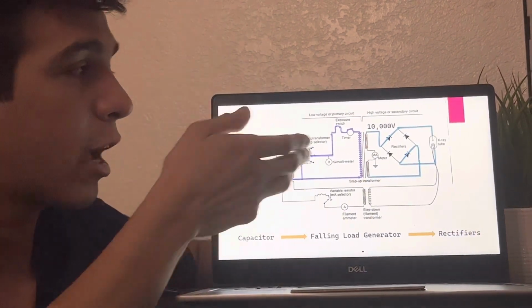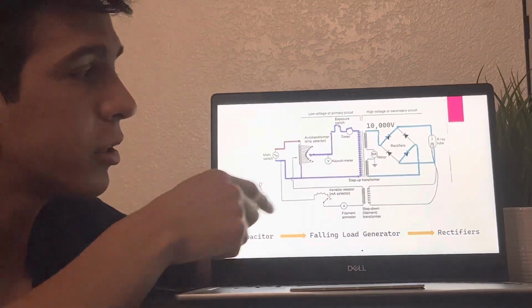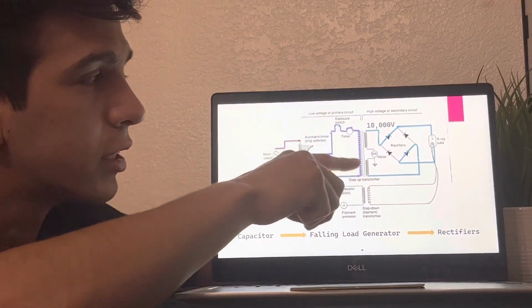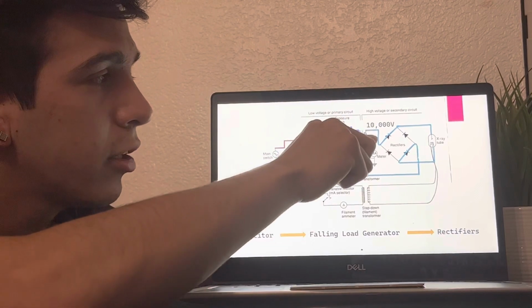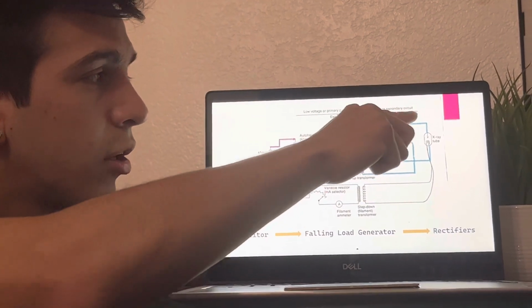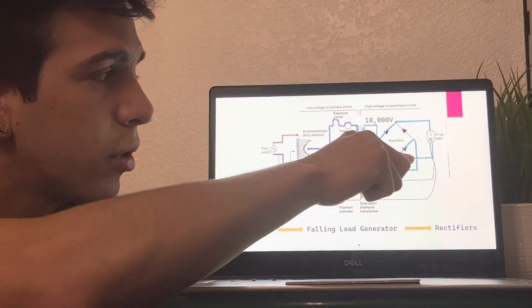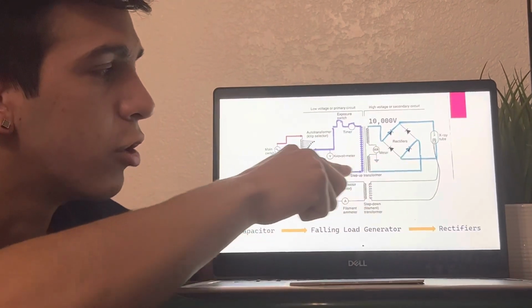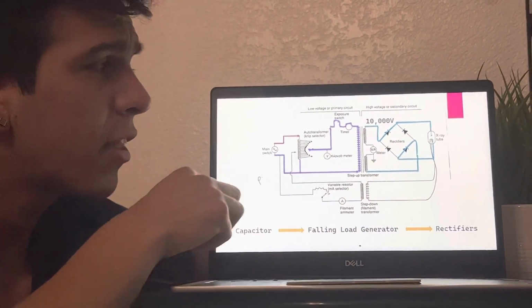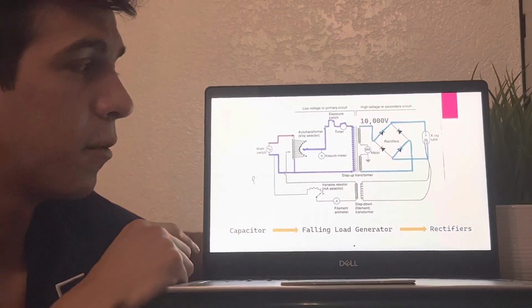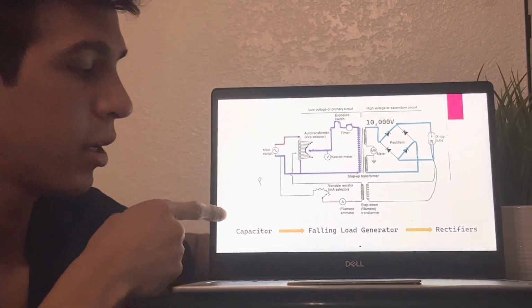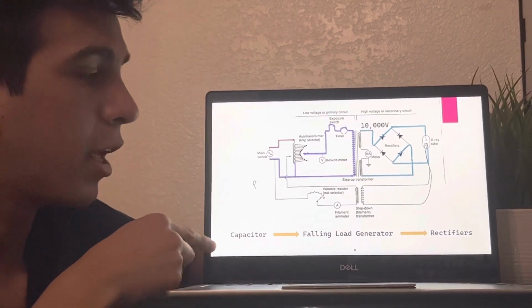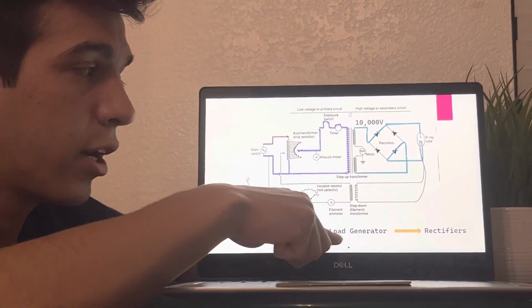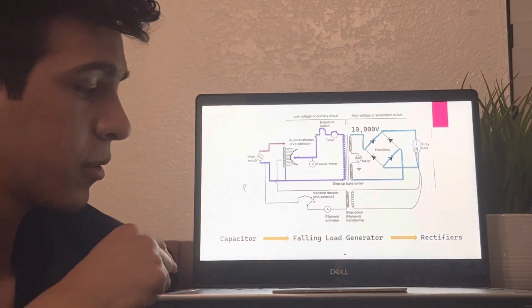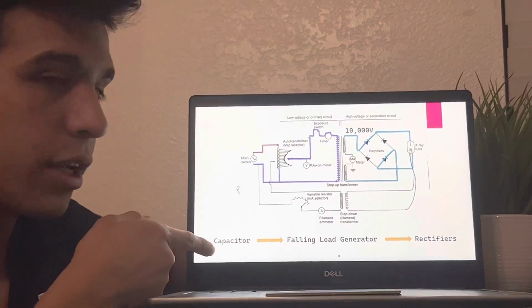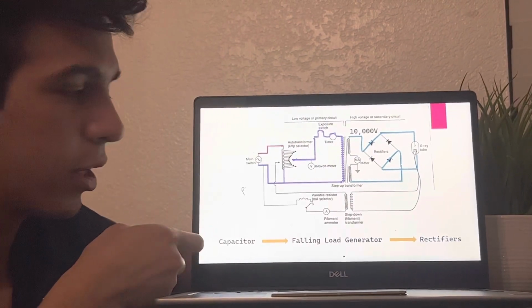And then now we have reached the 10,000 volts. Same thing, it's going to flow over to this side. It's going to start up here, go through these diodes, through the X-ray tube, and then just continue to follow the path. And then as it does this, the electricity is going to be stored in the capacitor and then go over to the falling load generator and then through the rectifiers. The capacitor is just the storage place for it.